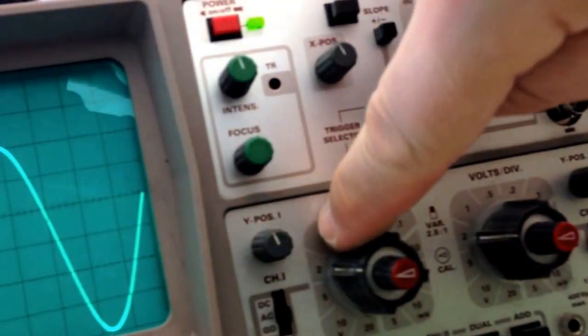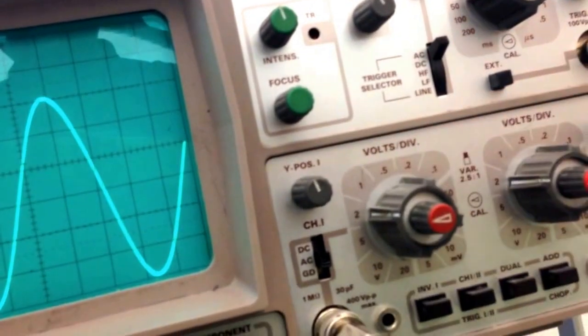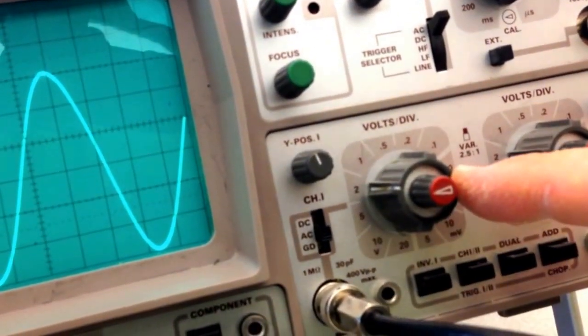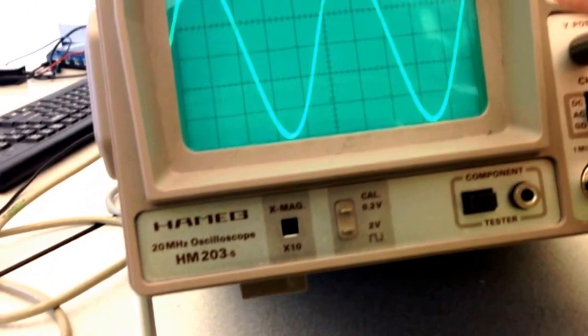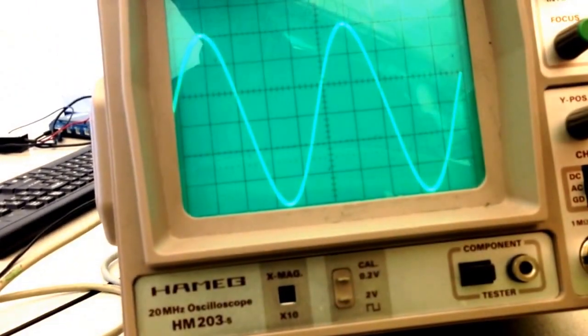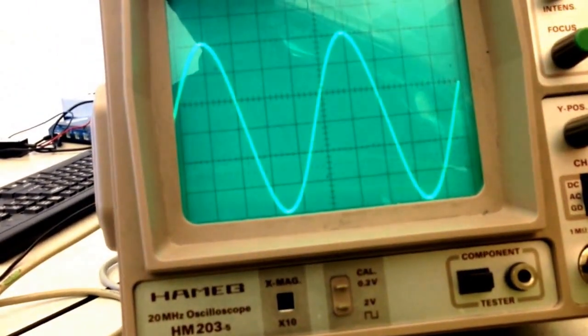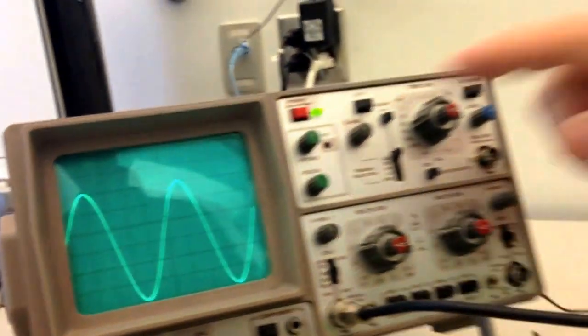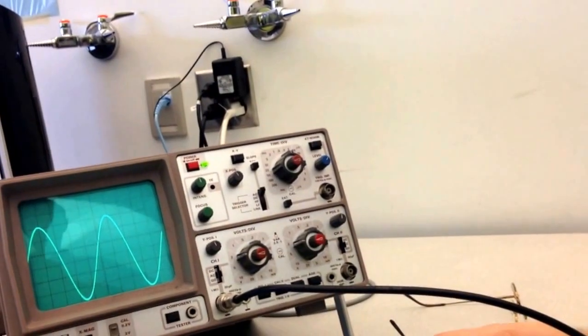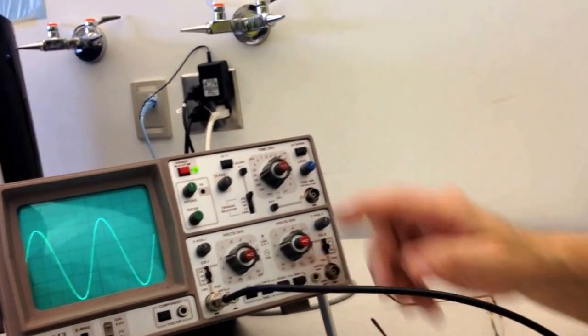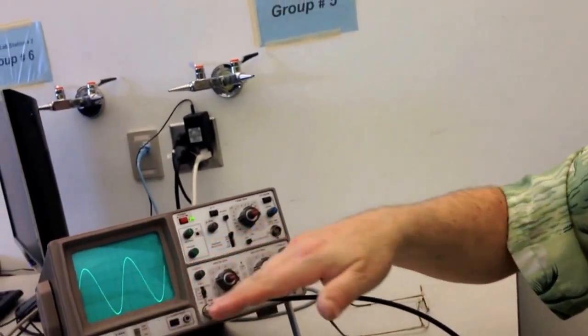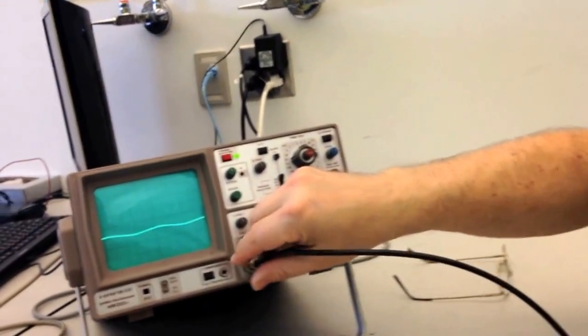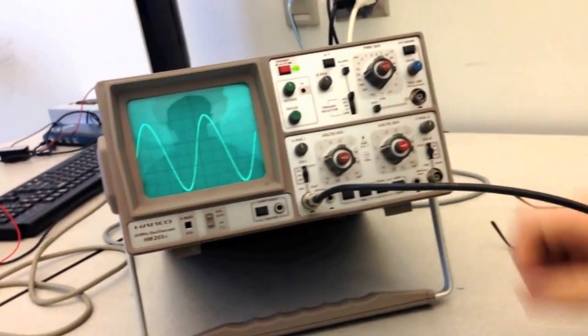Now, our magnification knob is set to two volts per division. So, if the magnification is two volts per division, and on the screen, the peak to peak voltage is six divisions. Six divisions times two volts per division. Divisions will cancel out. And our peak to peak voltage will be 12 volts. Now, what is our amplitude? Amplitude, by definition, is half the peak to peak voltage. So, our voltage or our amplitude will actually be six volts.